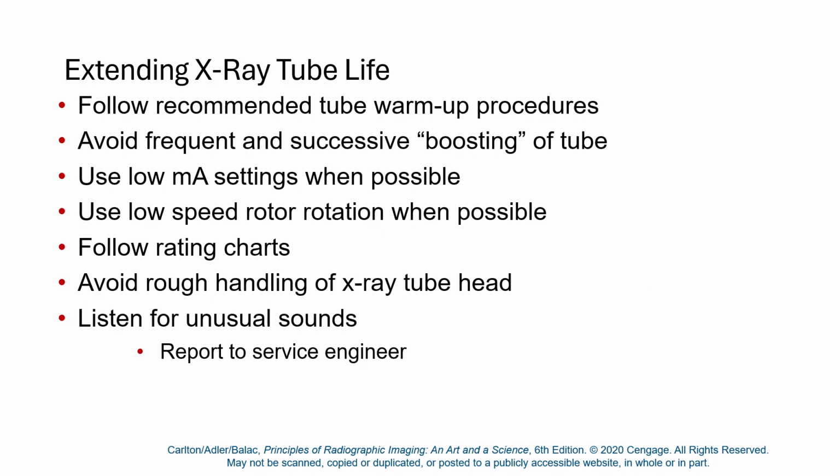Okay. So how do you extend tube life and avoid damaging your tube? You're going to follow tube warm-up procedures. Some of the manufacturers have made this an automatic software process that locks you out from even starting an exam until you perform a warm-up procedure. I think that's very smart. Okay.